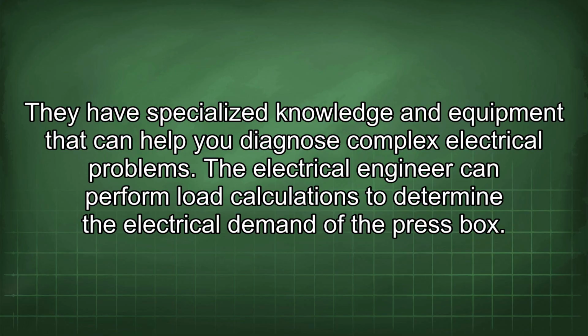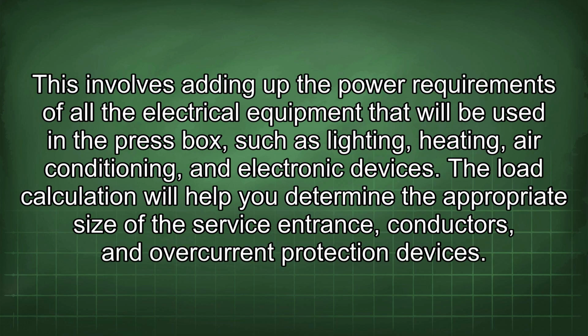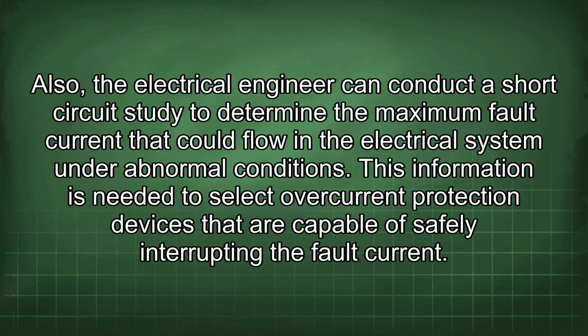The electrical engineer can perform load calculations to determine the electrical demand of the press box. This involves adding up the power requirements of all the electrical equipment that will be used in the press box, such as lighting, heating, air conditioning, and electronic devices. The load calculation will help you determine the appropriate size of the service entrance, conductors, and overcurrent protection devices. Also, the electrical engineer can conduct a short circuit study to determine the maximum fault current that could flow in the electrical system under abnormal conditions. This information is needed to select overcurrent protection devices that are capable of safely interrupting the fault current.